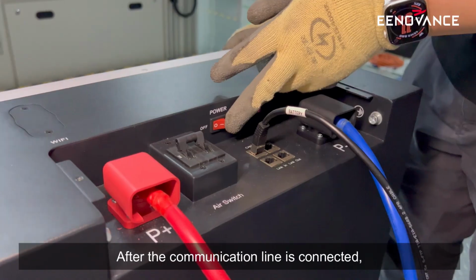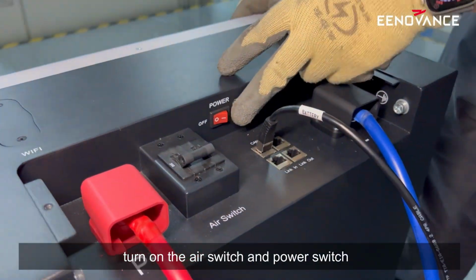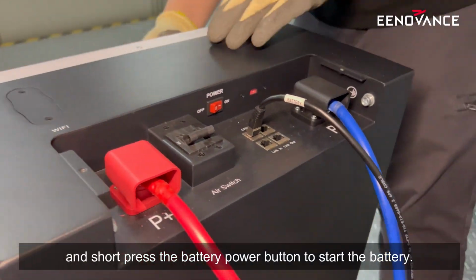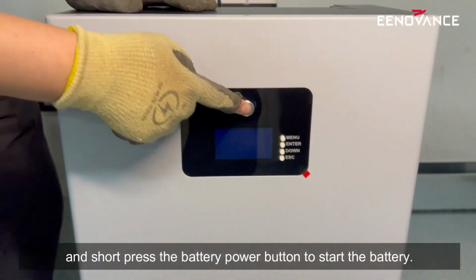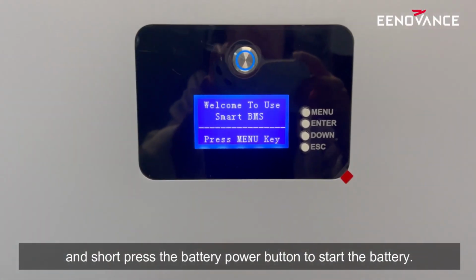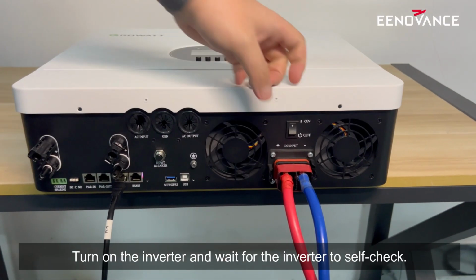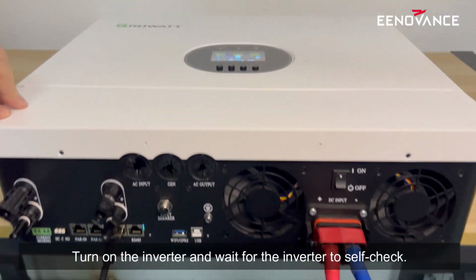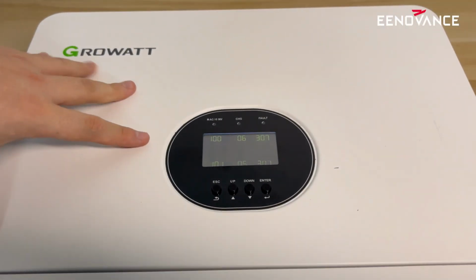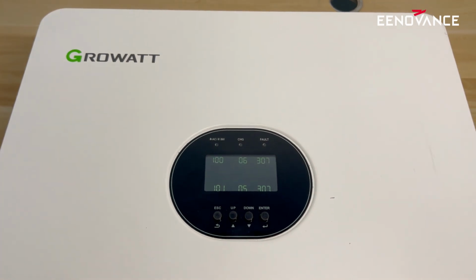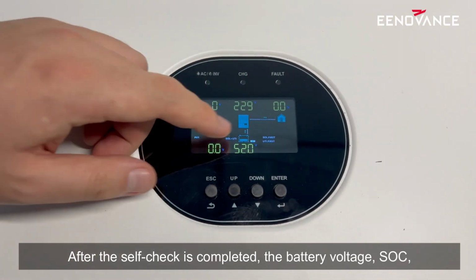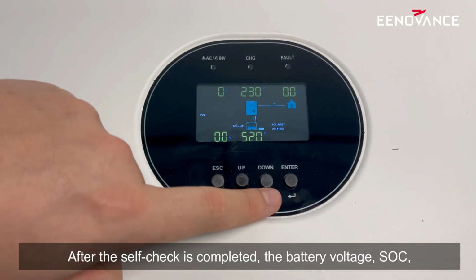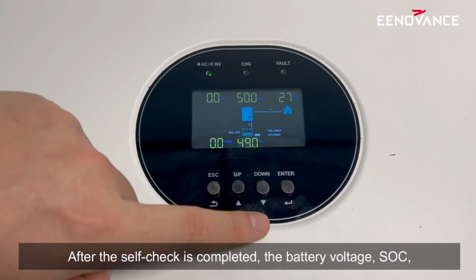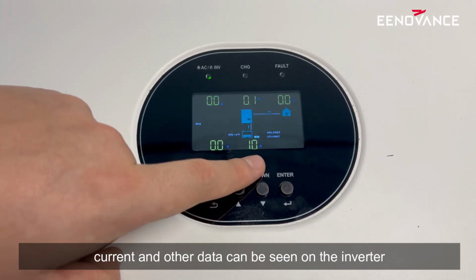After the communication line is connected, turn on the air switch and power switch, and short press the battery power button to start the battery. Turn on the inverter and wait for the inverter to self-check. After the self-check is completed, the battery voltage, SOC, current and other data can be seen on the inverter.